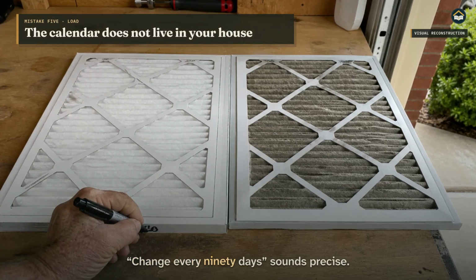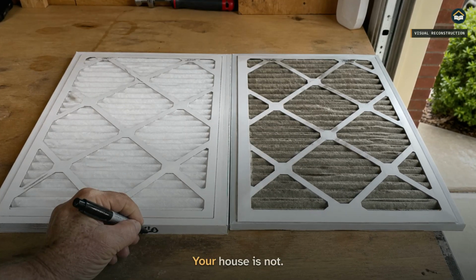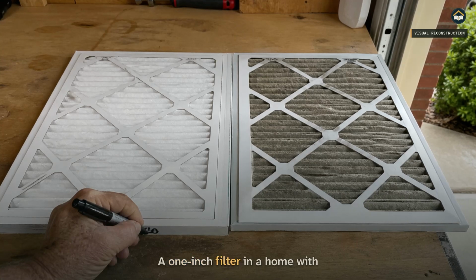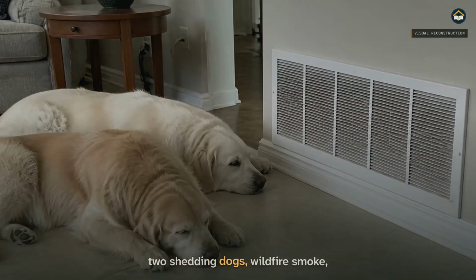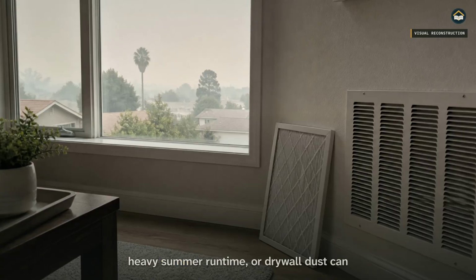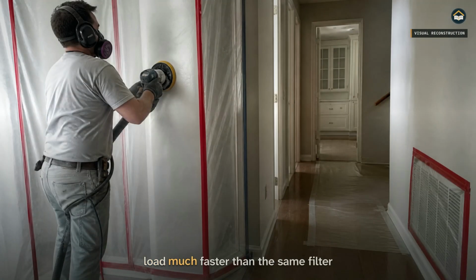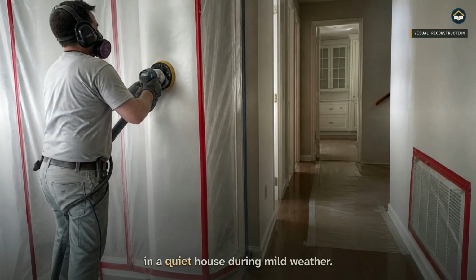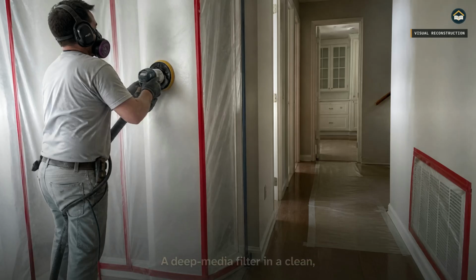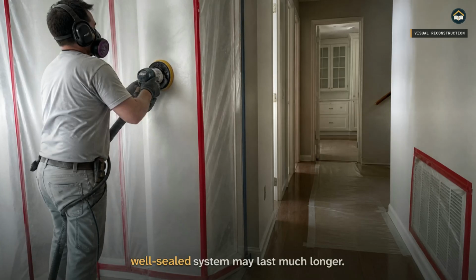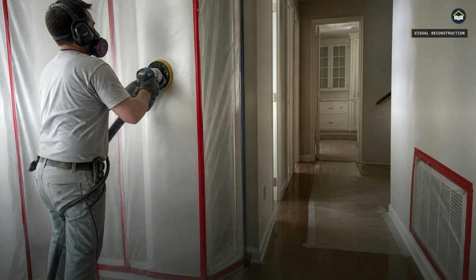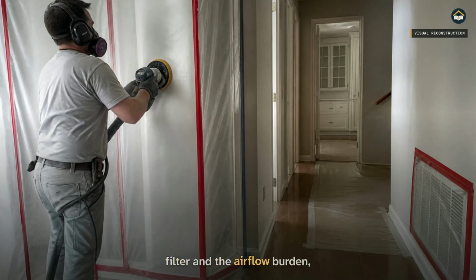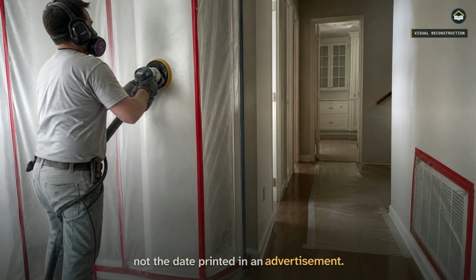Change every 90 days sounds precise. Your house is not. A 1-inch filter in a home with 2 shedding dogs, wildfire smoke, heavy summer runtime, or drywall dust can load much faster than the same filter in a quiet house during mild weather. A deep media filter in a clean, well-sealed system may last much longer. What matters is the condition of the filter and the airflow burden, not the date printed in an advertisement.